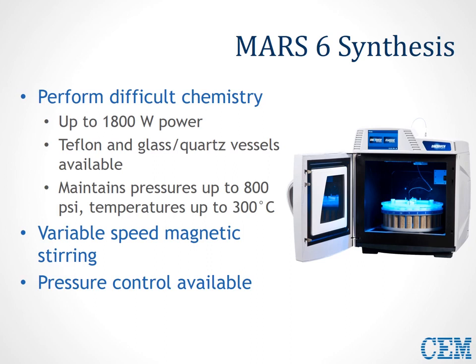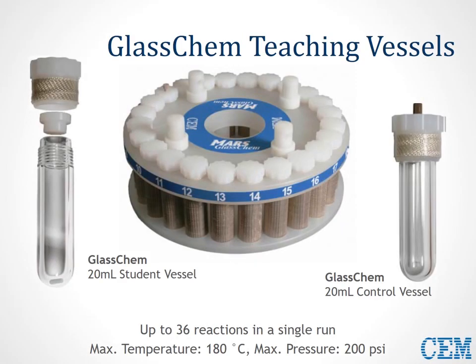The custom-engineered microwave cavity of the MARS-6 is constructed of high-grade solid steel with a heavy-duty spring-mounted door with safety interlocks. Should an accident occur, students are out of harm's way as the incident is contained within the cavity and the instrument turns itself off to prevent further damage. The most common vessel set seen in classrooms is the GlassChem vessel set, which comes with 24 or 36 easy-to-assemble three-part vessels. Students prepare the reaction, insert the Teflon plug, then tighten the Teflon cap. Each vessel is placed in a numbered sleeve, the carousel is placed in the microwave, a method is programmed, and you're done. After the reaction finishes, the system cools the vessels to a safe temperature for handling. If you're using the CEM Organic Chemistry Lab Manual, this is the vessel set referenced for all MARS-6 synthesis versions of the experiments, though those experiments can be modified for different vessel types.